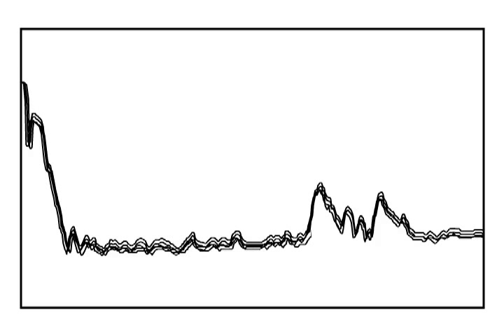The device overlays a number of echo profiles on top of one another. Then, using sonic or process intelligence, it combines these profiles into one average profile. The average profile reduces the noise floor and gives a more accurate indication of the true material echo.